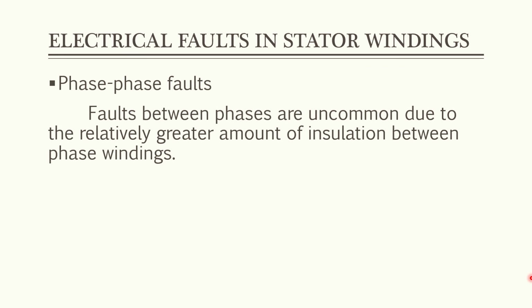Next, phase-to-phase faults between phases are uncommon due to the relatively greater amount of insulation between phase windings. But sometimes, though it is not common, when we overuse a machine and exceed the temperature limit, we are melting the insulation, and afterwards, when it is already melted, the conductors can attach to one another and can cause a fault. But it is very uncommon because we are very careful when it comes to temperature in a motor.